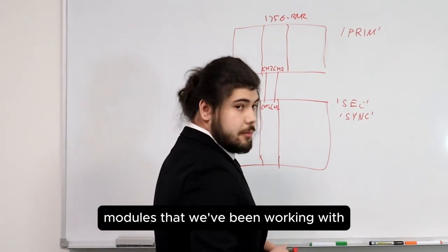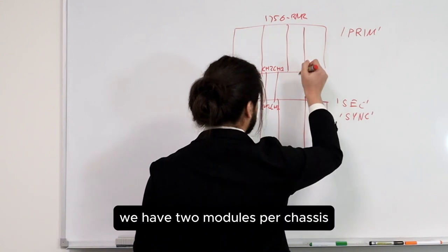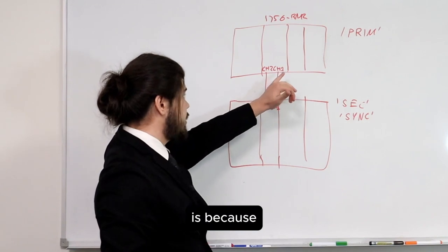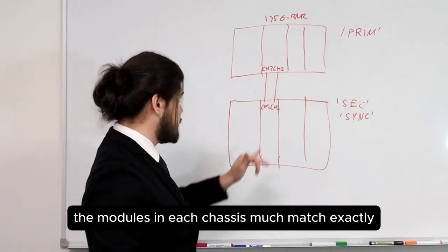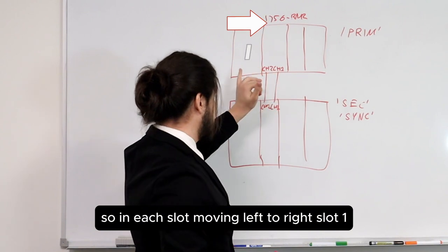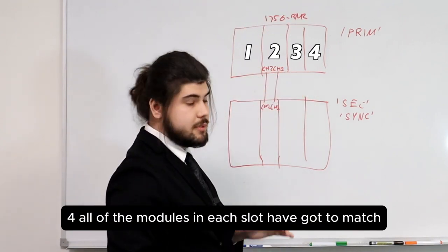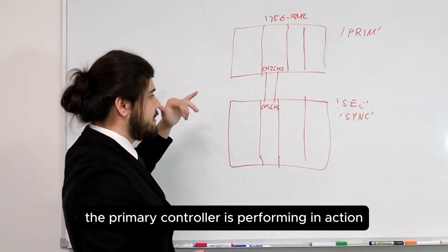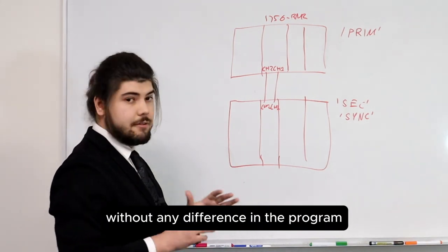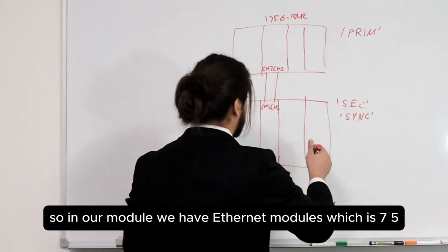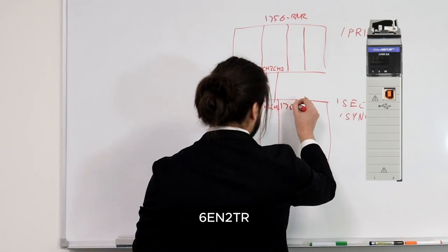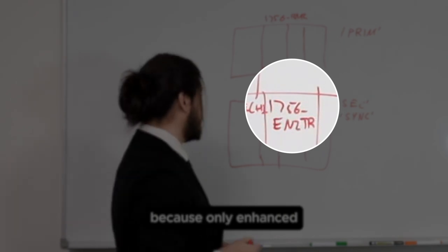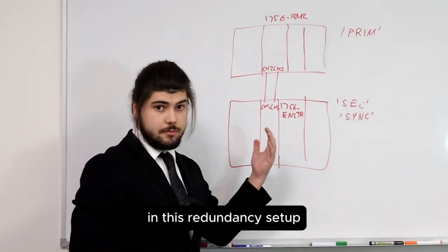The communication modules we've been working with are Ethernet modules. We have two modules per chassis, and the reason is that the modules in each chassis must match exactly. So in each slot moving left to right, all of the modules in each slot have got to match. The idea is that if the primary controller is performing an action, the secondary controller can immediately perform that action without any difference in the program or hardware configuration. In our module we have two 1756-EN2TR Ethernet modules. The 'two' is important because only enhanced Ethernet communication modules can be used in this redundancy setup.